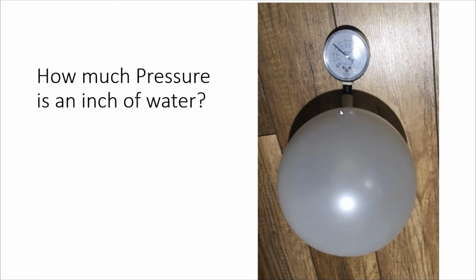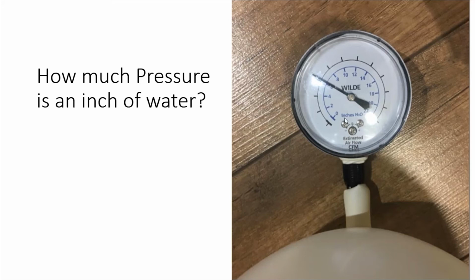Here's a bit of a feel for how small it is. This is just a normal balloon that I blew up, and I put a static pressure gauge on it, and you can see that reads 6 inches of water. So when we're dealing in inches of water, we're talking about the type of pressure that the human lung can put out, not the type of pressures that an air compressor can put out.